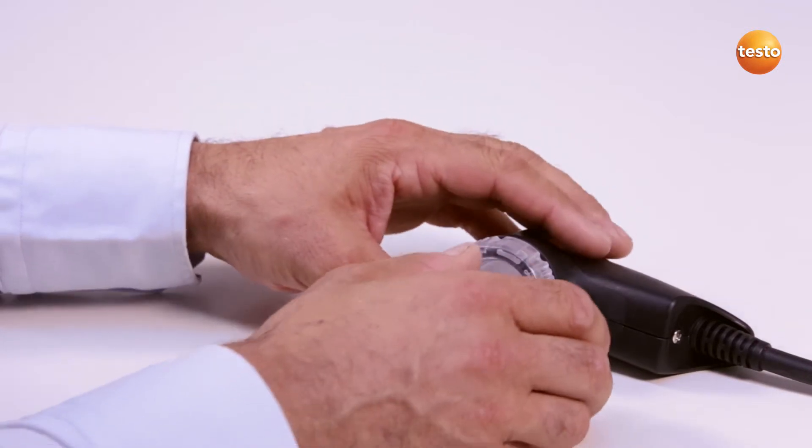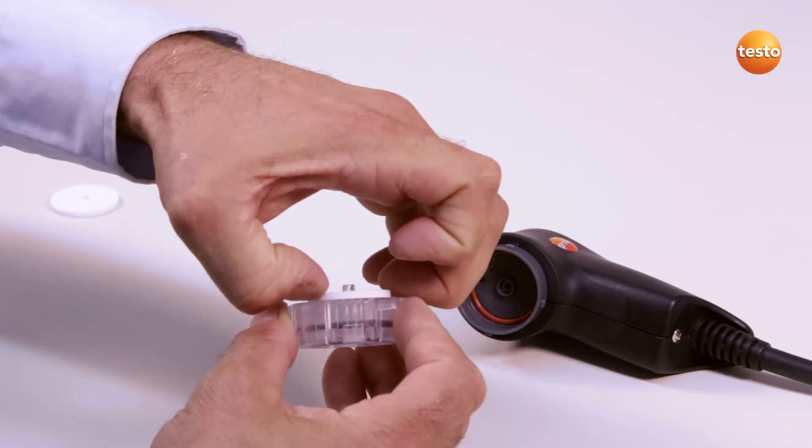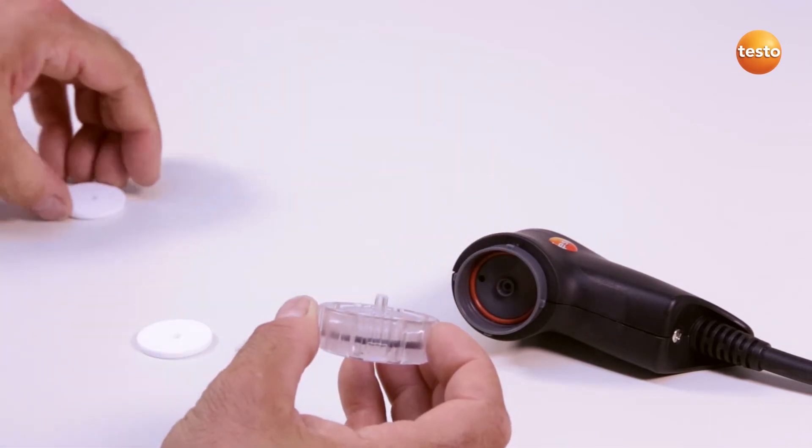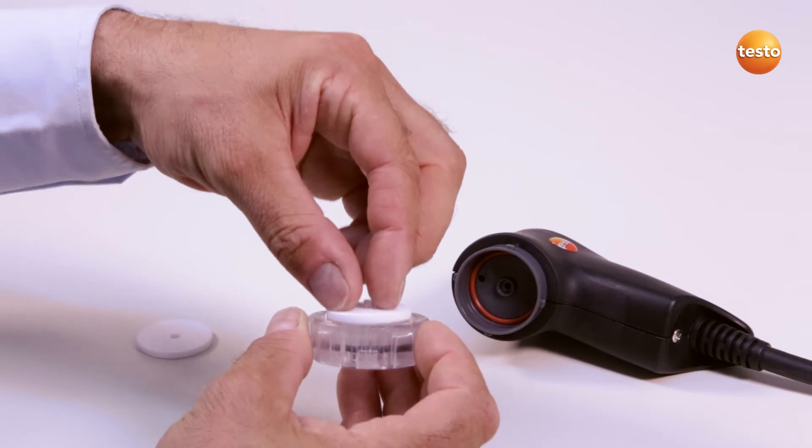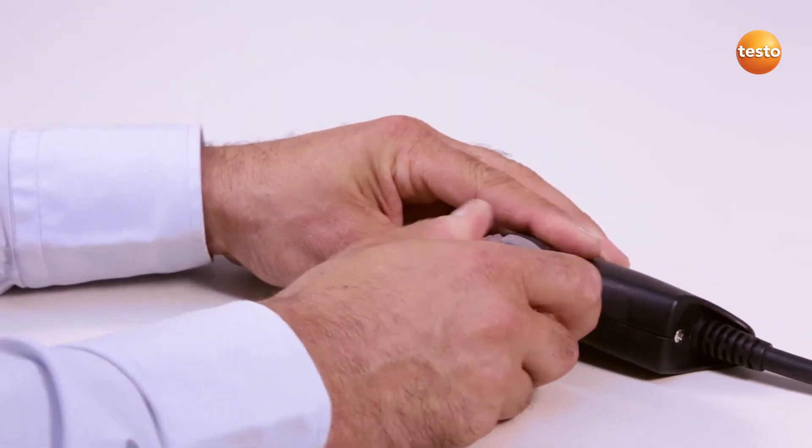In order to exchange the particle filter, I open the filter chamber by turning slightly anti-clockwise. I remove the filter disc and replace it with a new one. I finally replace the filter chamber and close it.